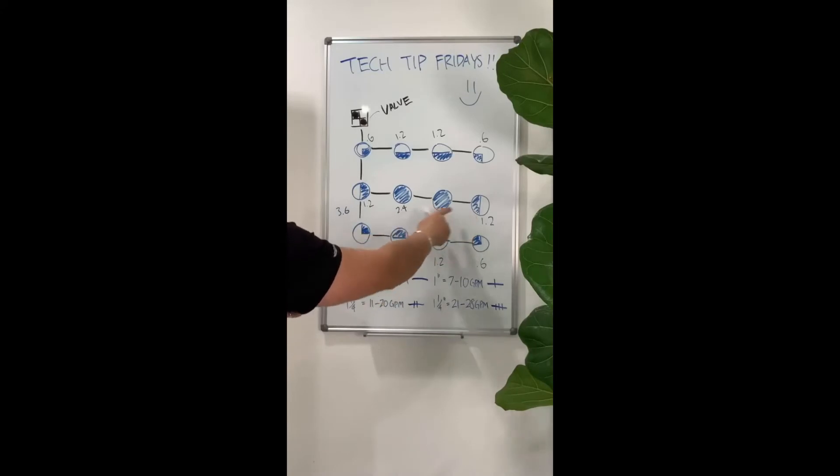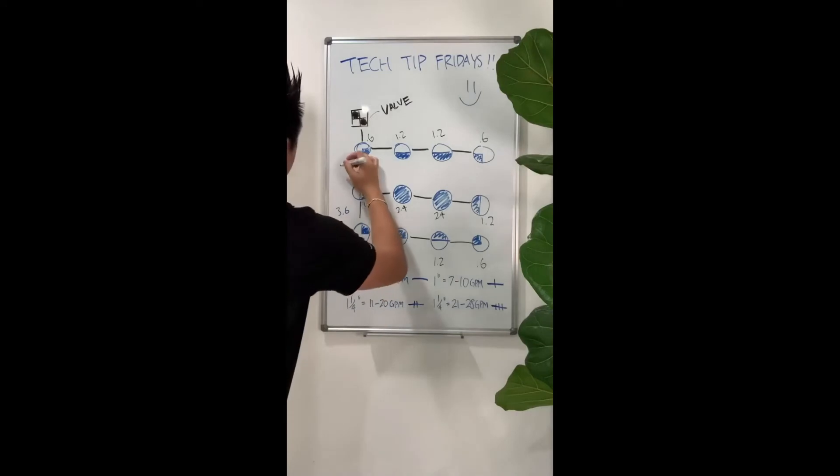Now the next one that we want to calculate is the section in the middle. So we got 1.2 plus 2.4 plus 2.4 plus 1.2. So that's 7.2 GPMs running through this section right here. And being that everything before that is between 1 and 6 GPMs, these are still three-quarter inch. And we take the total of that, which is 7.2 GPMs plus 3.6 GPMs to get this section. So we got about 10.8 GPMs running through this section.